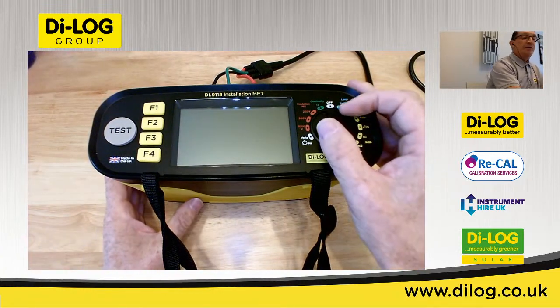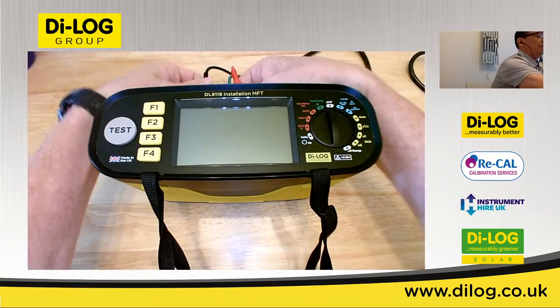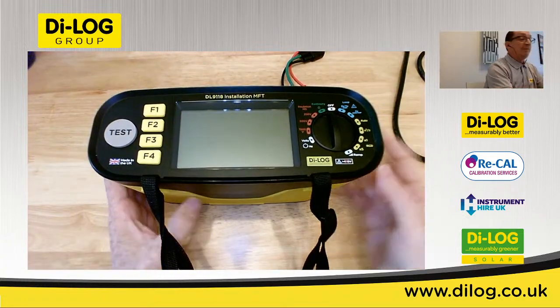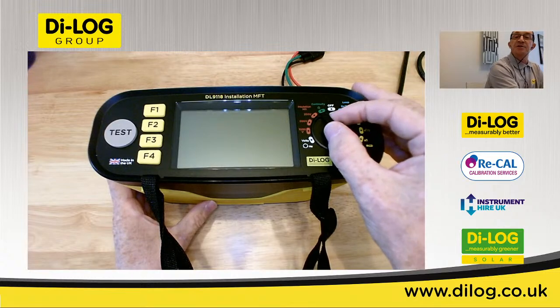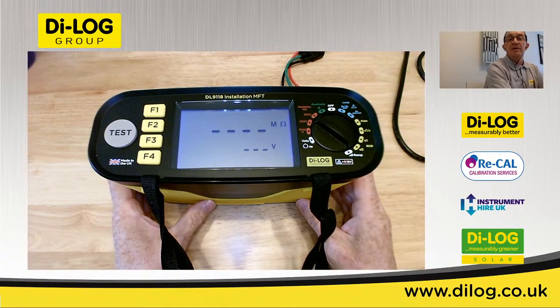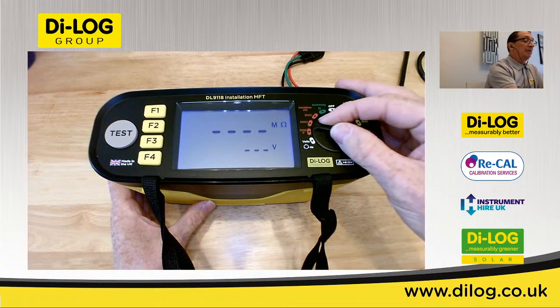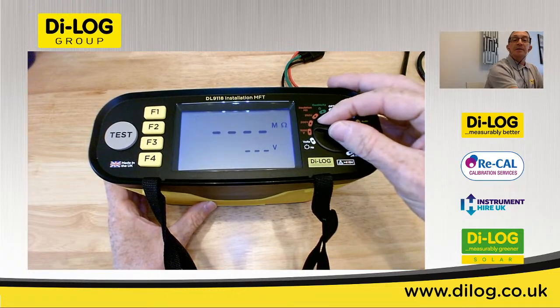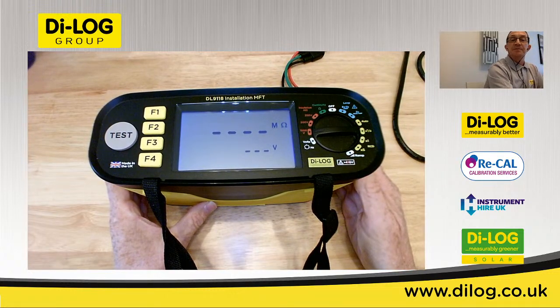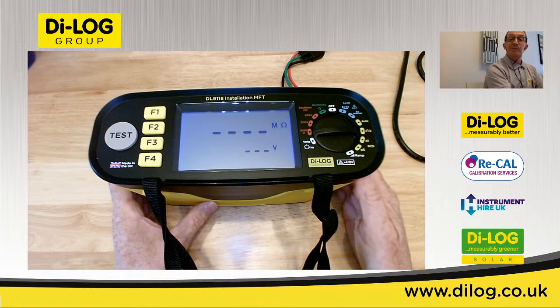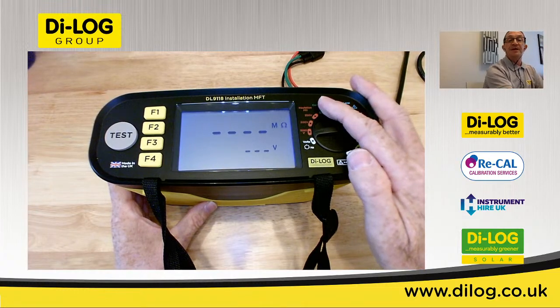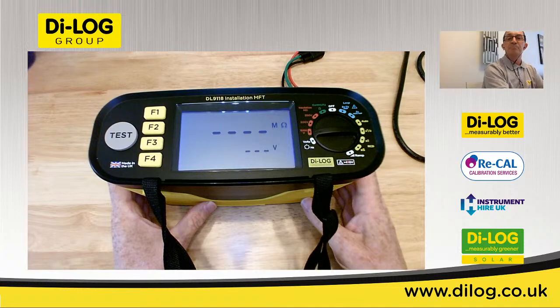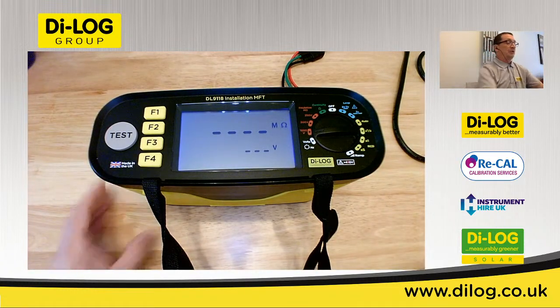So moving from continuity, on the 9118 model, we have 3 insulation test voltages: 250 volt, 500 volt, and 1000 volts. The 9110 model is limited to 250 and 500 volts, more than enough for your average domestic and light commercial installations.